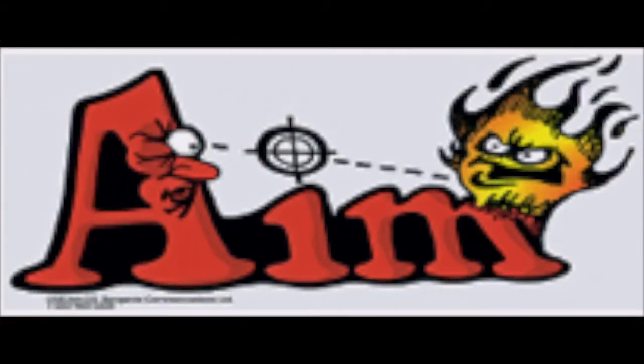The PASS method for using the fire extinguisher starts with pulling the pin. Stand back 8 to 10 feet from the fire. You'll then aim the nozzle at the base of the fire and squeeze the handle to release the agent. Sweep the base of the fire with the agent.